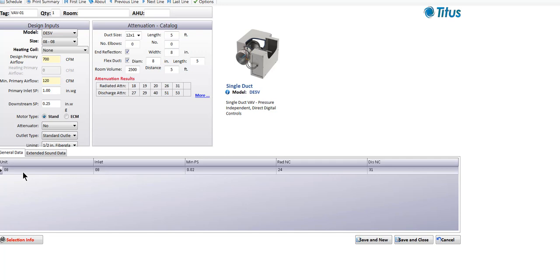The reason I use 2,000 feet per minute is that if air isn't moving through ductwork at more than 2,000 FPM, I shouldn't be self-generating any noise. In our industry we're allowed to go as high as 3,000 FPM, but I like to limit myself to 2,000 to keep static pressure drop and sound levels low. I also don't want to oversize my inlet duct — I try to keep it close to 2,000 so I don't have to worry about turn-down at the low end, which can make the inlet flow sensor signal too low for the controller to read, resulting in controllability problems and hunting.